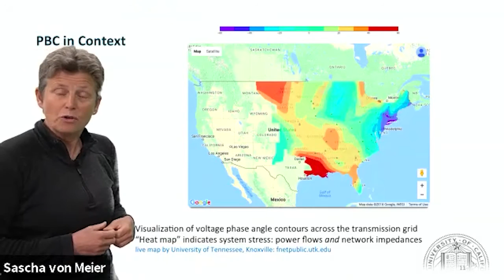This is one of the great resources provided by the University of Tennessee at Knoxville with their FNET monitoring system that shows you basically in real time with very short delay these voltage phase angle differences, which across the entire Eastern grid go over many, many degrees, because we're talking about many megawatts and long distances. So large impedances, or especially inductive reactances on the transmission lines. But you can see that power is generally flowing from areas of positive phase angle to areas of negative phase angle.